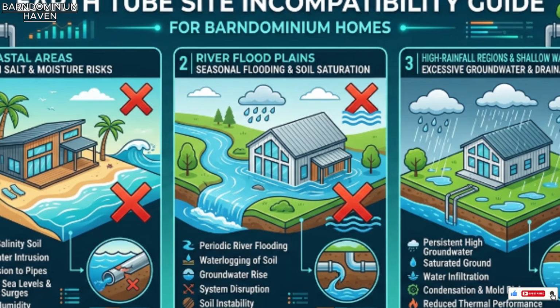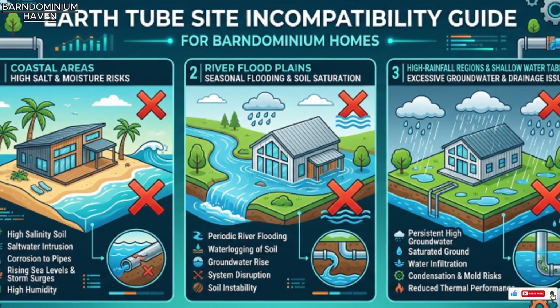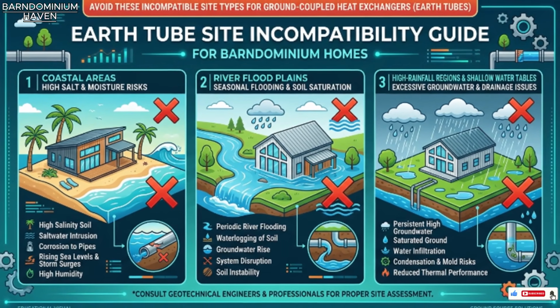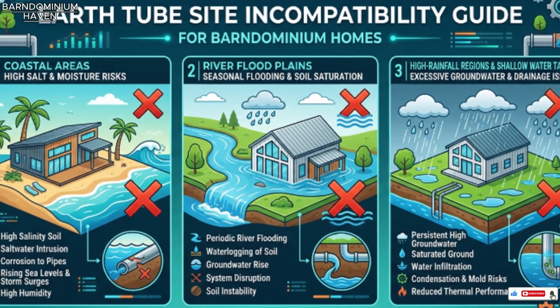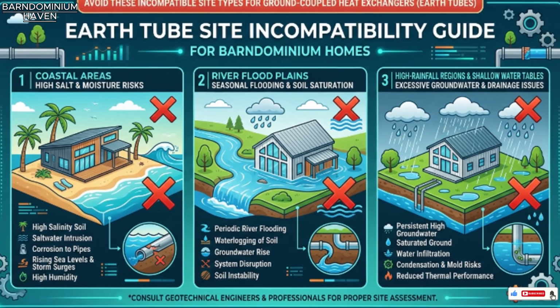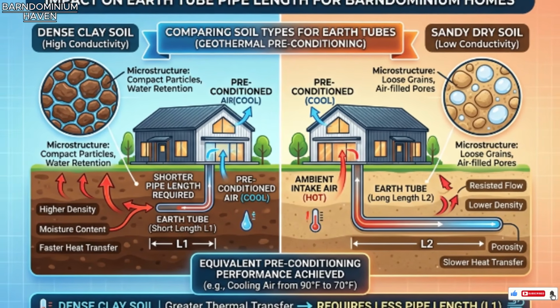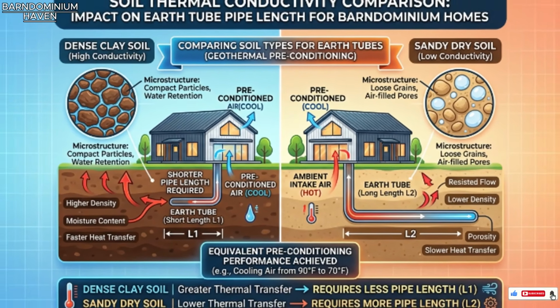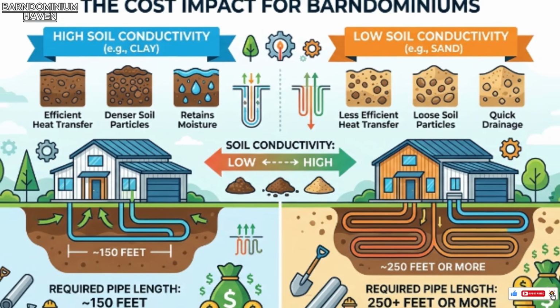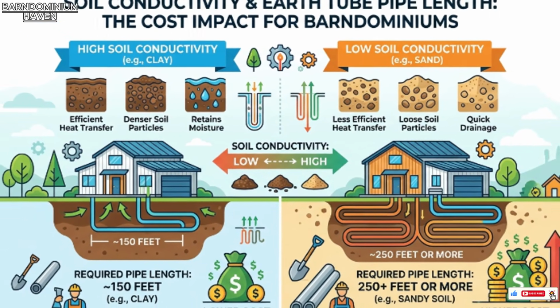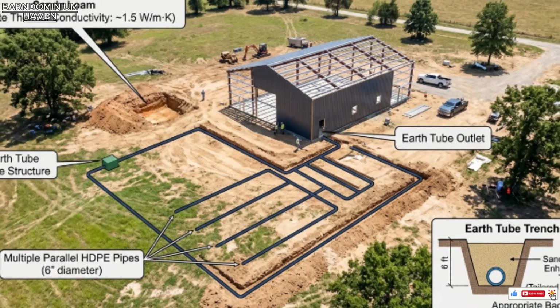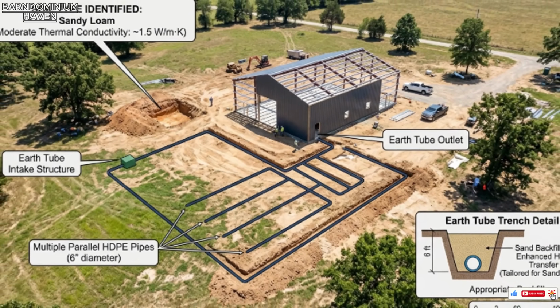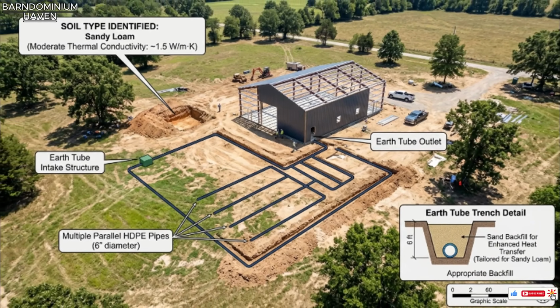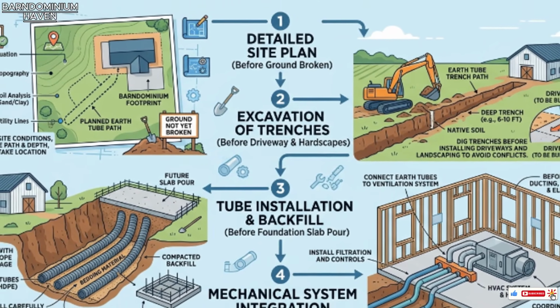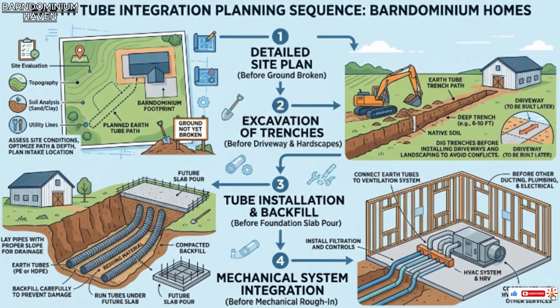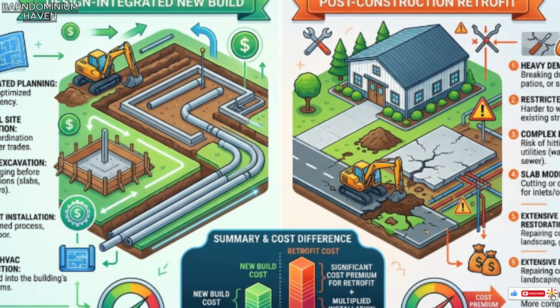A site where the water table is within 6 feet of the surface, common in coastal areas, river flood plains, and high rainfall regions, cannot accommodate an earth tube system at an effective depth. Soil thermal conductivity varies. Sandy or dry soils have lower thermal conductivity than dense clay or moist soils, meaning the air-to-soil heat exchange is less efficient. And the required pipe length to achieve the same preconditioning performance increases significantly. In low-conductivity soils, a system that requires 150 feet of pipe in clay soil may require 250 feet or more to achieve equivalent performance. A cost difference that changes the system's financial case significantly.